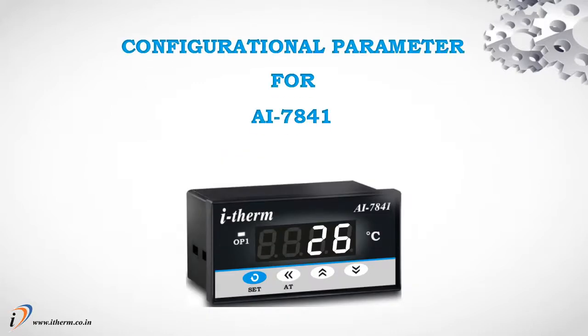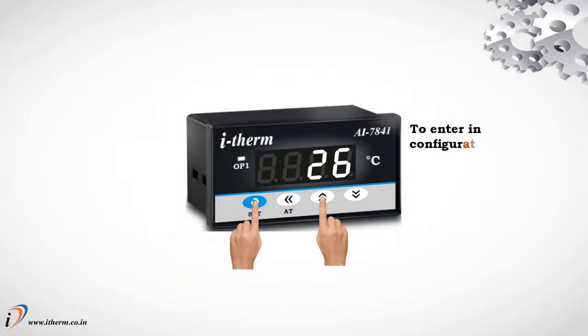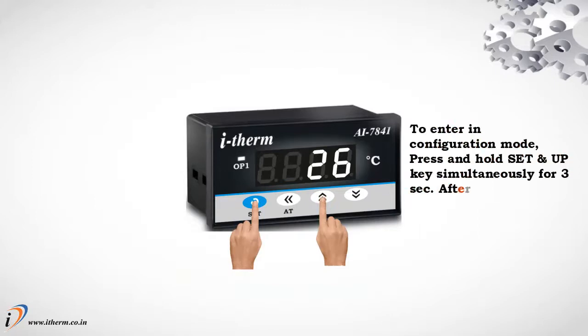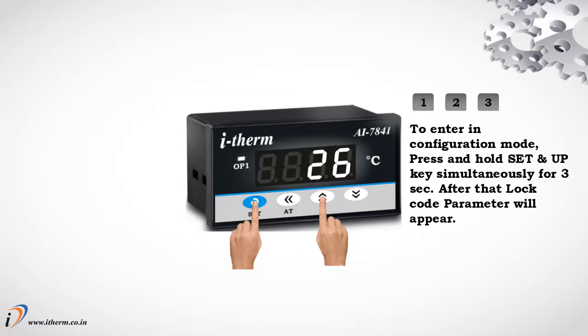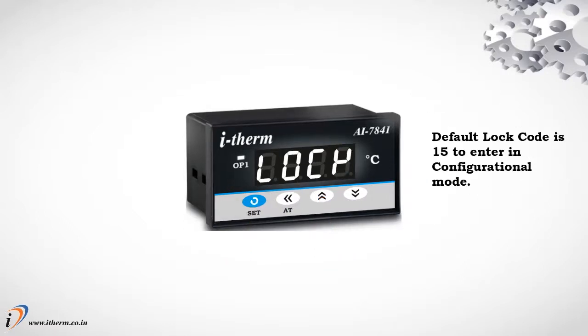Configurational parameter for AI7841. To enter in configuration mode, press and hold Set and Up key simultaneously for 3 seconds. After that, lock code will appear. Default lock code is 15.